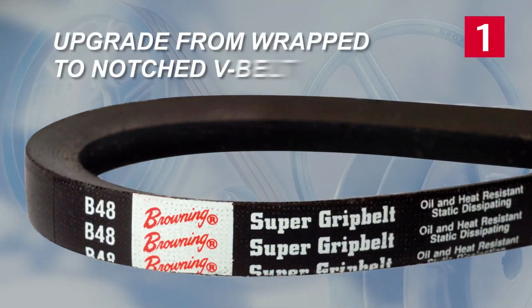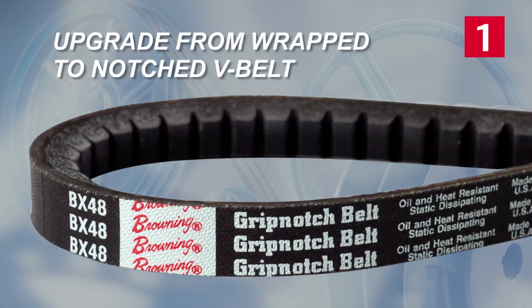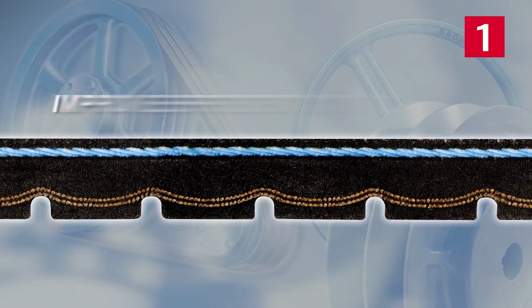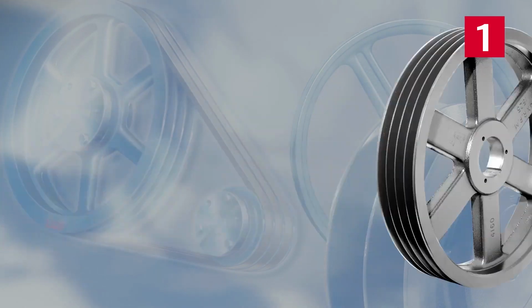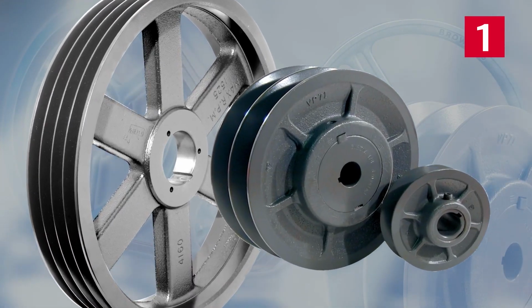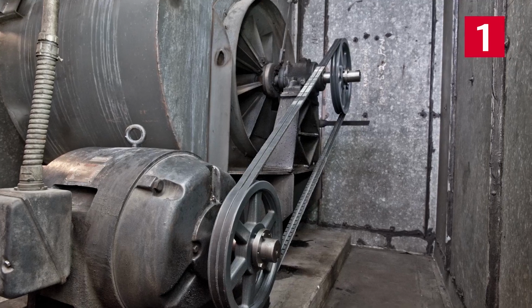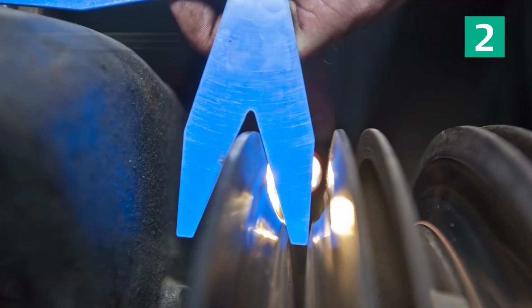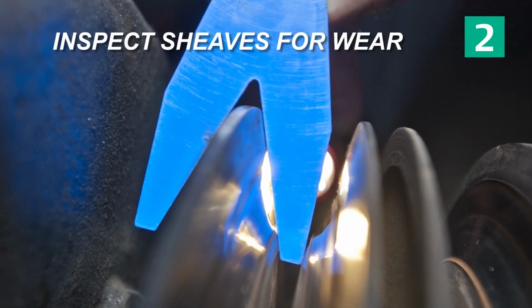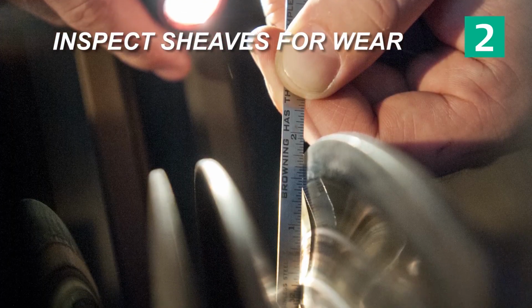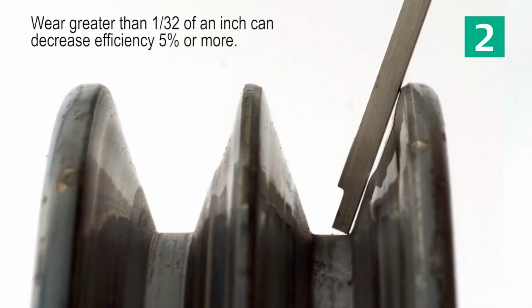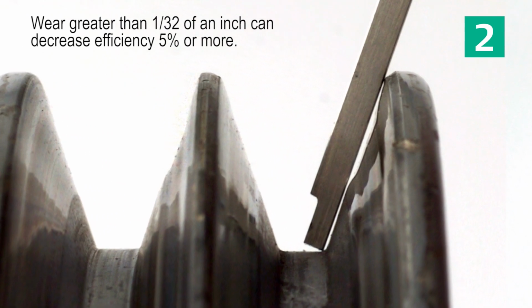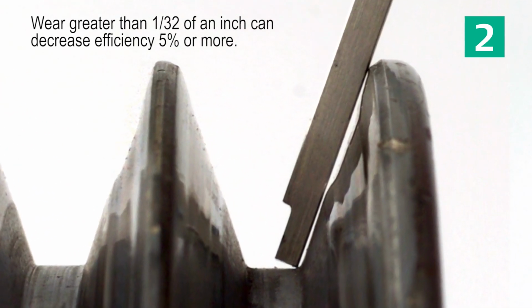The first is to upgrade from a wrap to a notch-style V-belt and improve your efficiency about 3%. They utilize the same pulleys or sheaves that the standard wrap V-belts do, and it's a drop-in replacement. The second step is to inspect sheaves for wear. Worn sheaves allow belt slip. Wear greater than 1/32 of an inch can decrease efficiency 5% or more.